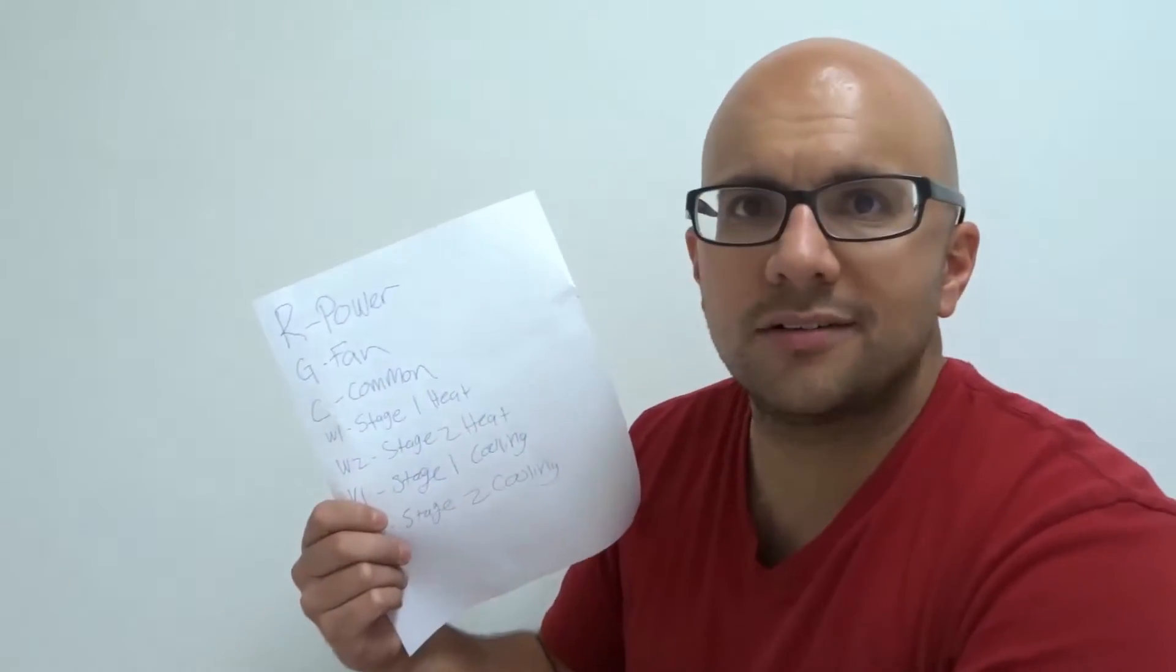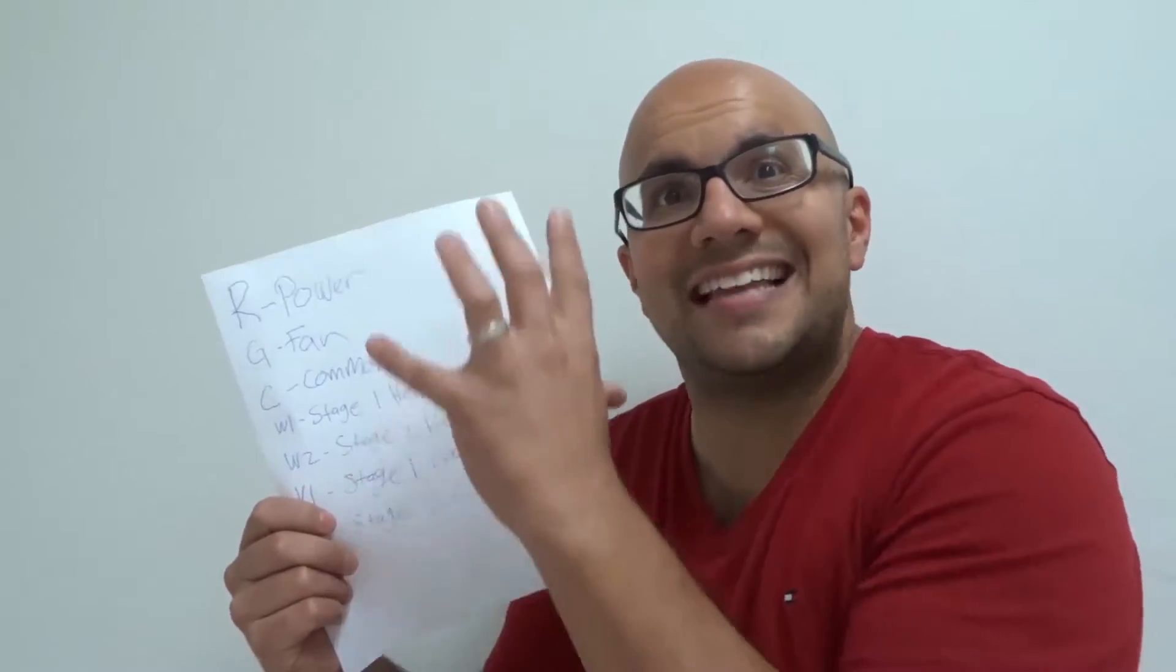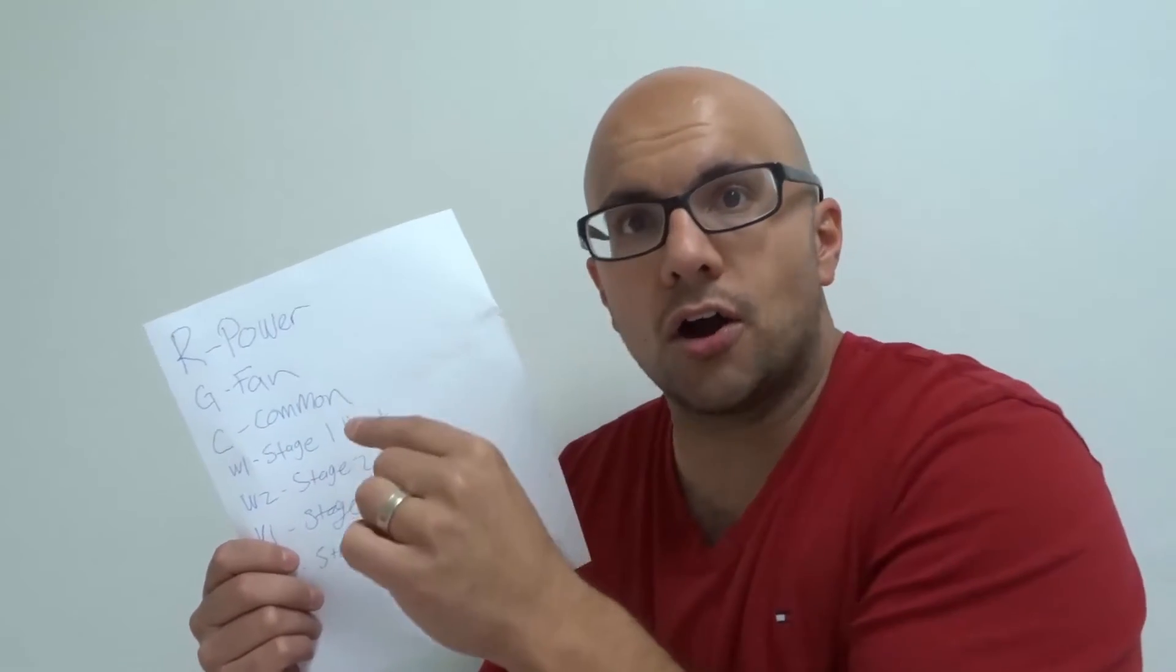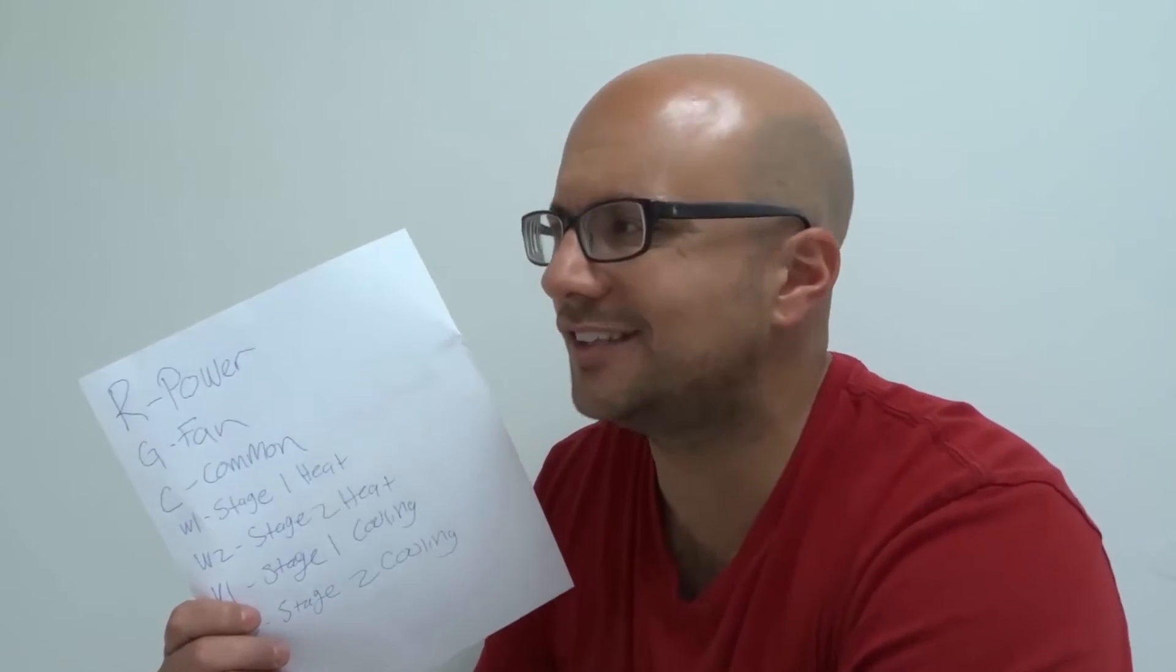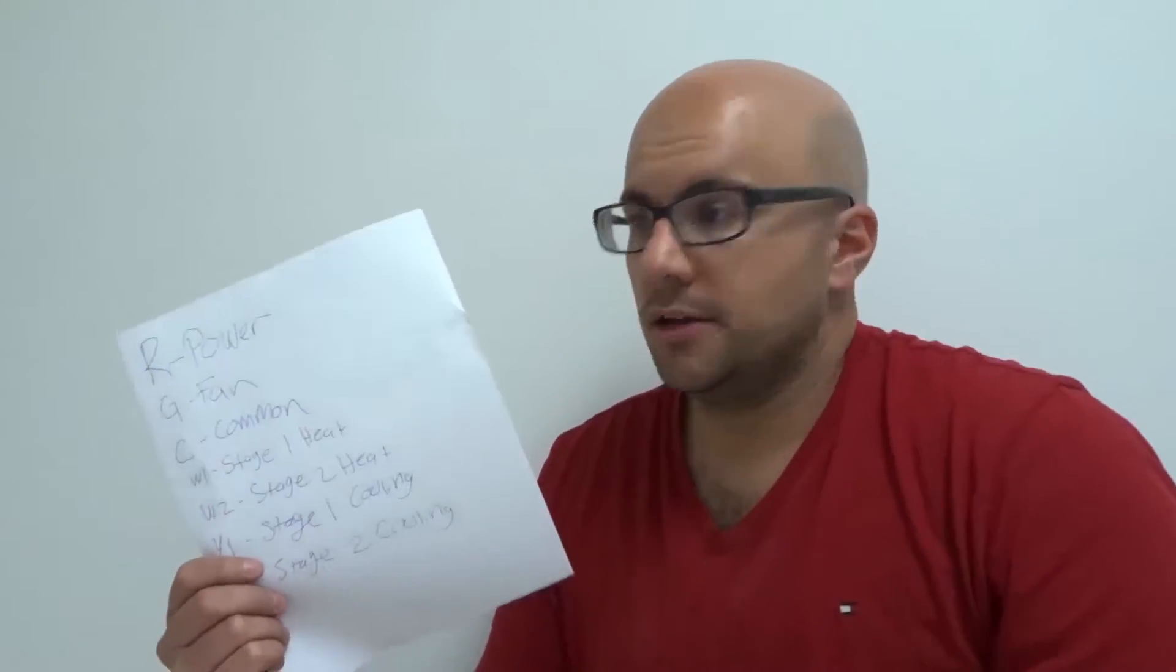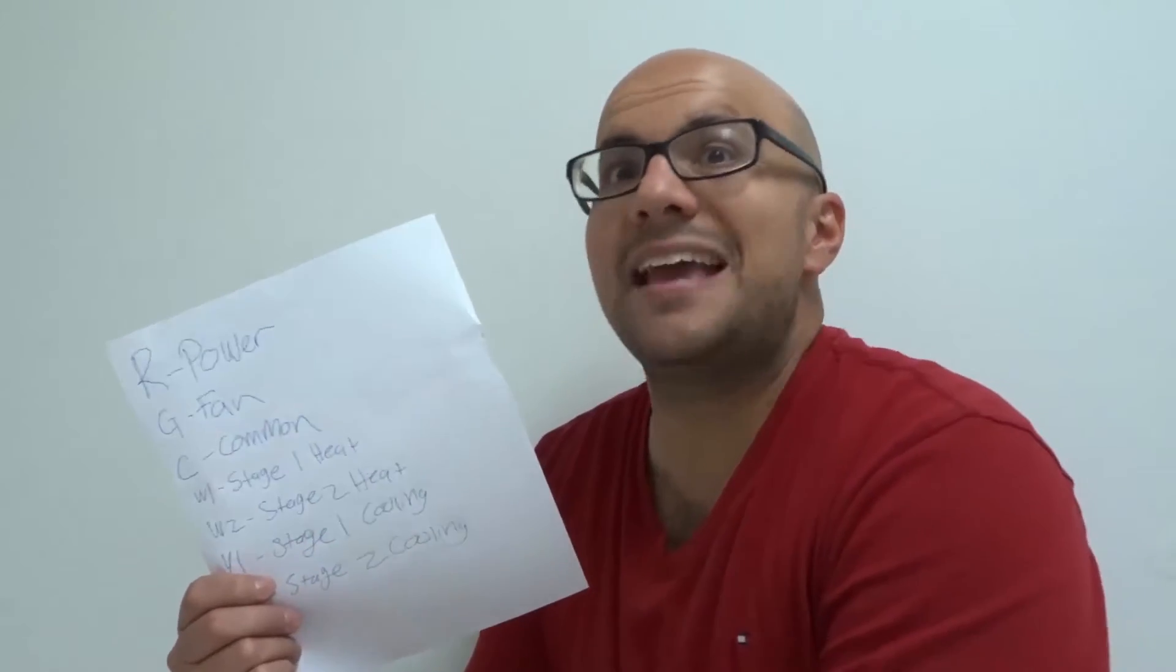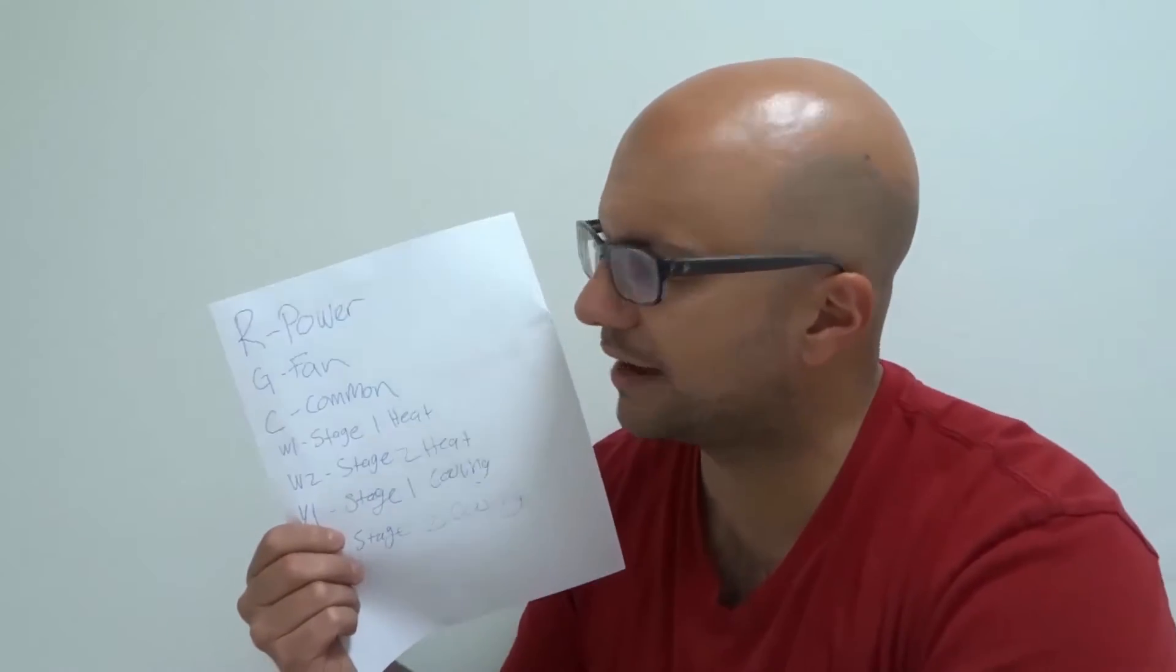So R is for power. Now, here's the thing. Any of these wires can technically be any color. But the wire that's connected to the R terminal on your thermostat and the R terminal on your motherboard where your furnace is, that is going to be the power wire. Once again, it can be any color. Commonly people will use a red for R, but it can be any color. So R is for your power. I'm going to go through them and then I'll explain how they work.